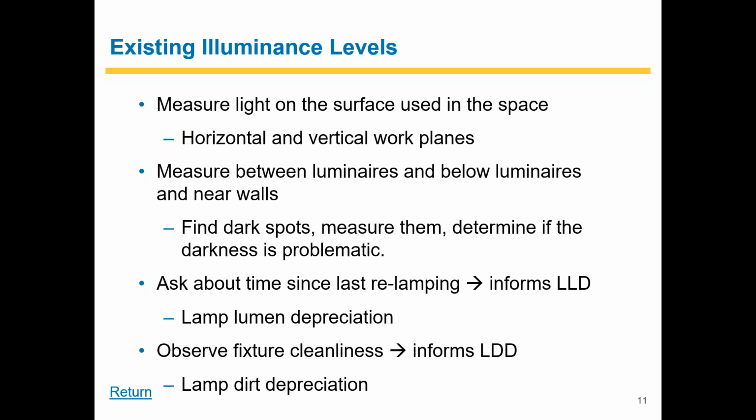I've done a lot of warehouse lighting retrofit projects where the lamps are being replaced on burnout, and as a result, the lamps that continue to run tend to have a really low light output relative to new lamps. When you compare the old light output, with lamps well beyond their expected useful life, against a new LED lighting product, of course the LED product is going to look much brighter. But LED lighting products should be designed for their end-of-life lumen depreciation, which generally speaking is a 30% light loss. That's how we get the L70 lamp life. So if we're having a 30% light loss and comparing it against a system that's been allowed to depreciate more than it should, you might not actually have a true apples-to-apples comparison.